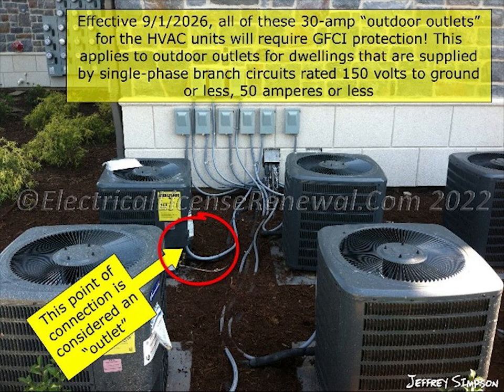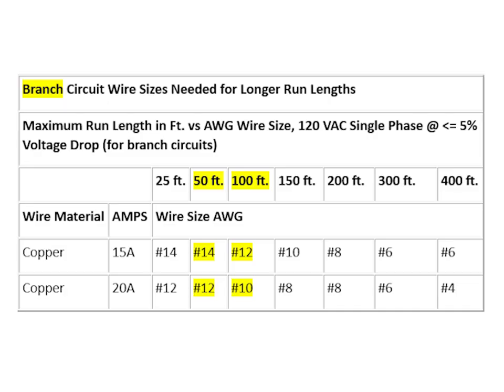There are also requirements for an external outlet for air conditioners. Under the GFCI requirements given earlier, these circuits require protection. Some discussion on wire sizing. Code requires a 15 amp circuit cannot have wire smaller than 14 gauge, and a 20 amp circuit cannot have wire smaller than 12 gauge. This is really a function, though, of length of run. If your run length is greater than 50 feet, you need to step up your wire gauge to the next size.